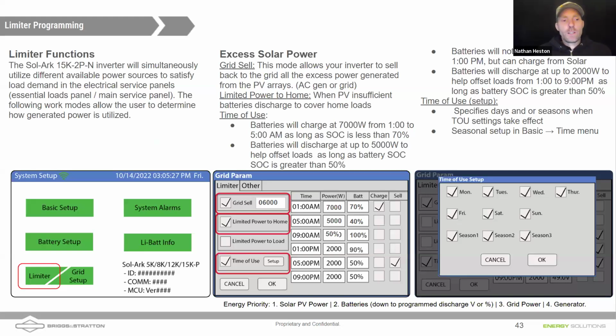You also have the ability, Daniel just mentioned, using the limiter, right? You have the ability to control the flow of power into and out of the batteries using a time of use setting. So under the limiter, let's talk about the different things that are here. That grid sell box here limits how much solar power can be sold back to the utility by backfeeding through the grid, right? So if you set that box to 6,000 watts, as is shown on the green screen, that will just limit how much power will come out of the inverter and go to utility.